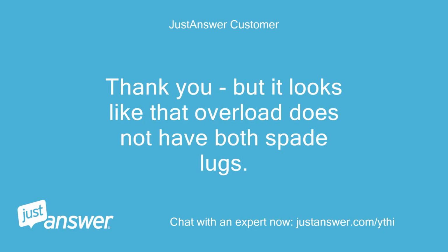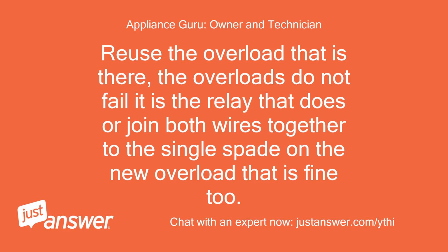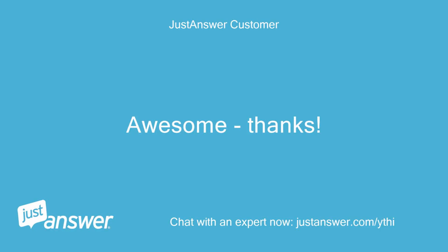Thank you, but it looks like that overload does not have both spade lugs. Reuse the overload that is there. The overloads do not fail. It is the relay that does, or join both wires together to the single spade on the new overload, that is fine too. Awesome, thanks.